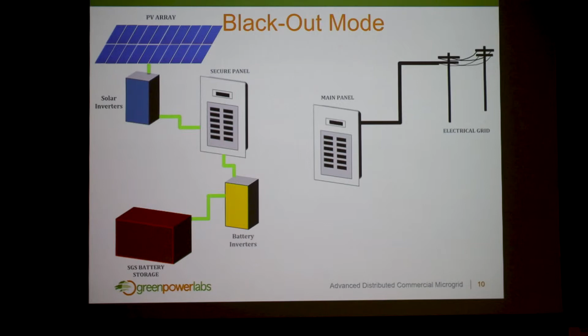But as I mentioned, there's a secure power panel here as well. That battery inverter is a grid generating inverter, so it's able to bring a signal online and allow the solar inverters to sync up to that. There's a neat feature there where there's actually frequency control from that battery inverter that allows the solar inverter to throttle its output to meet the loads on that secure power panel. So in terms of functionality, your primary source of energy powering loads on that secure power panel is PV. In the case that the PV system can't meet those loads, that's where the battery system steps in, and then it syncs back online once the grid's been reconnected.